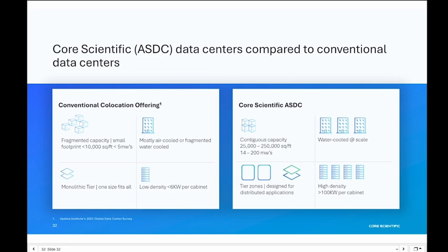Number two, a lot of these data centers built in the last 20 years are predominantly air cooled, so getting water cooled at scale can be difficult. Even providers that advertise DLC or water cooled to the rack are highly fragmented—if a data hall only has 1 megawatt of capacity, you're only delivering 1 megawatt of water cooling anyway, and it's scattered around the facility, not optimized for customers' high powered AI training workloads.